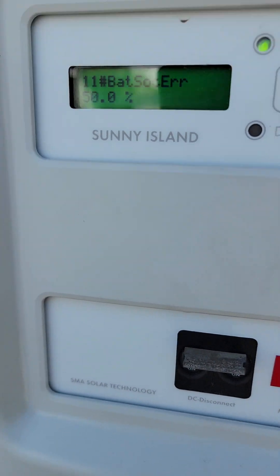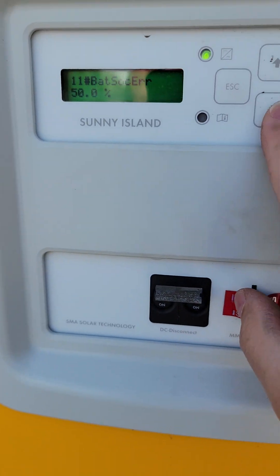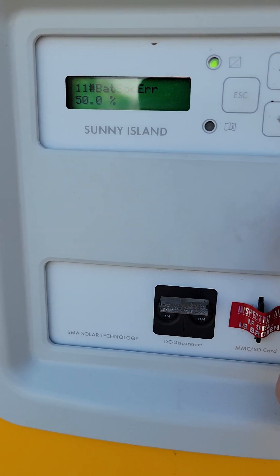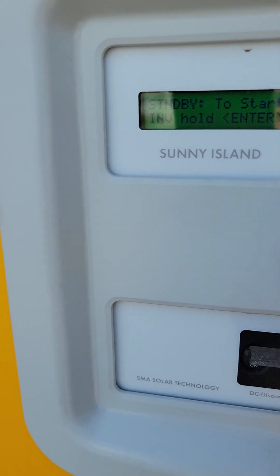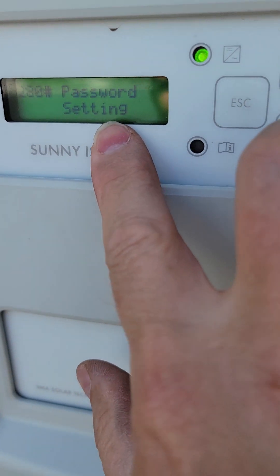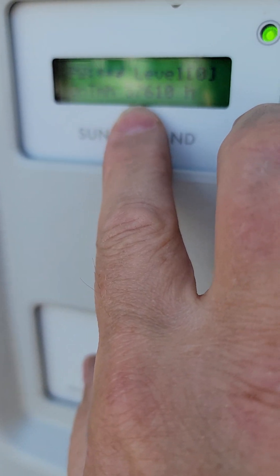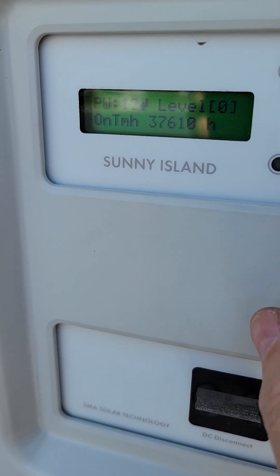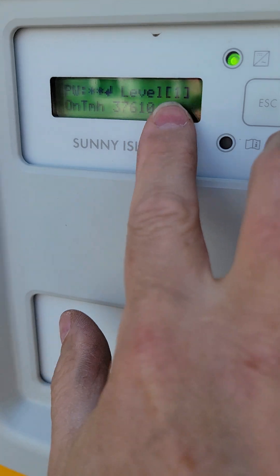Now there are two things we need to change. The first thing is we need to change how many amps can go into the battery. In order to do that, I actually have to go all the way to the top, hit down arrow to go into settings. We're going into installer mode, which you go all the way down to password settings and then hit enter. You add those numbers up, which is 3 plus 7 plus 6 plus 1 — that's 17. So as I hit the up arrow and enter 17, you'll see this level zero go to level one. We're now in installer mode.